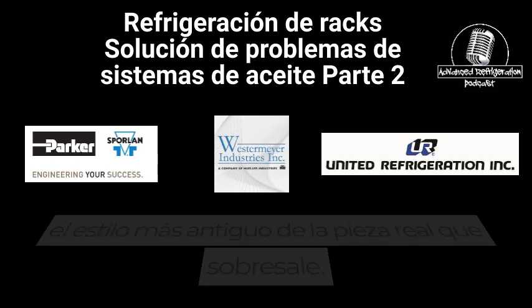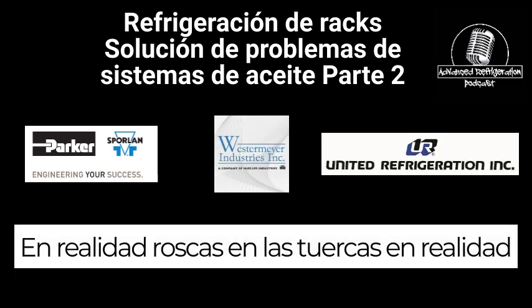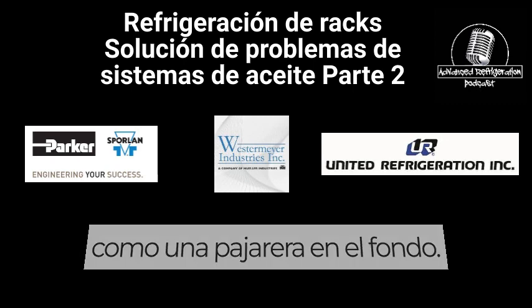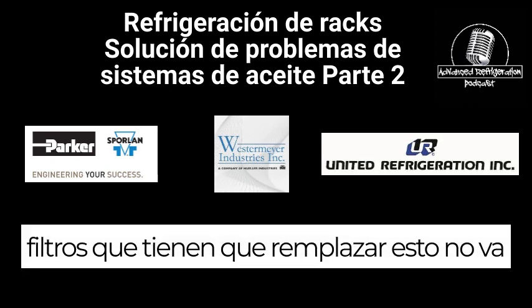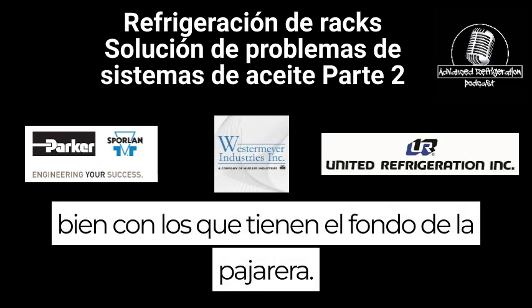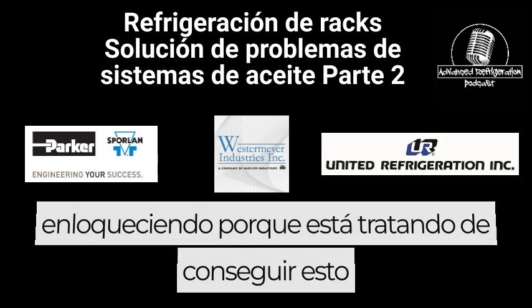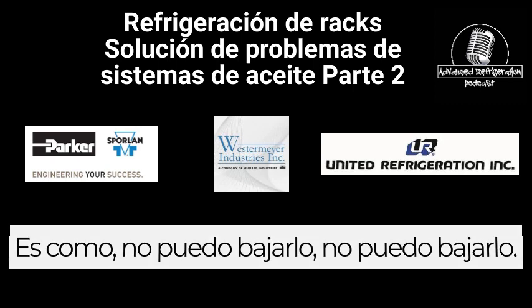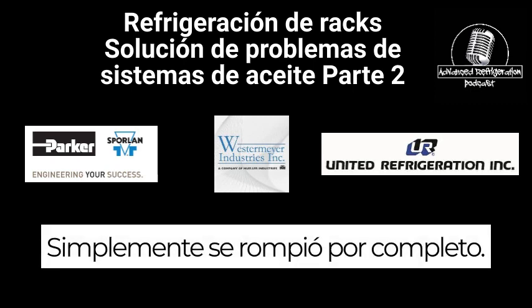Also be mindful on the Temprite oil separator, on the older style, the piece that sticks up actually threads on the nut to enclose that coalescing filter. The older style had almost what looked like a birdhouse at the very bottom. Now the newer Temprites do not have that, but the filters that they have to replace this don't go well with the ones that have the birdhouse at the bottom. I had a technician call me up freaking out because he's trying to get this oil coalescing filter on this piece. He's like, I can't get it down. And when he tried to get it down, he broke it. It just completely broke off.